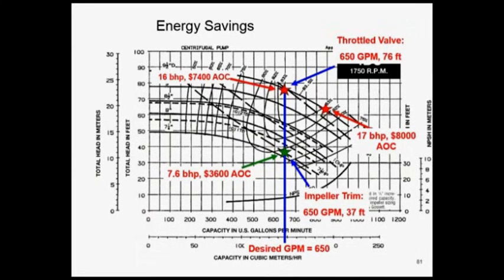And let's look at some numbers here. I like numbers when you pull all this together. This is extremely critical, you get this last slide here. In other words, I was running at $8,000, 17 brake horsepower when I just turned it on. If I throttled it with a throttle valve, I could push it back up to the original design point of 650 GPM at 76 feet of head, and I dropped it to 16 brake horsepower. And your cost now is $7,400. I saved $600. But when you did the right thing, engineers do the right thing.